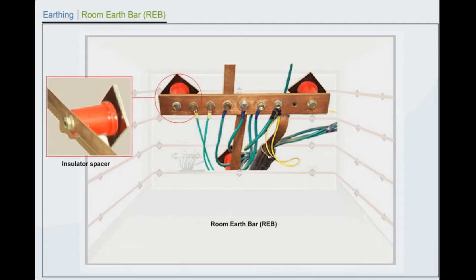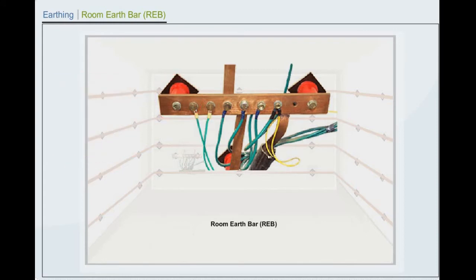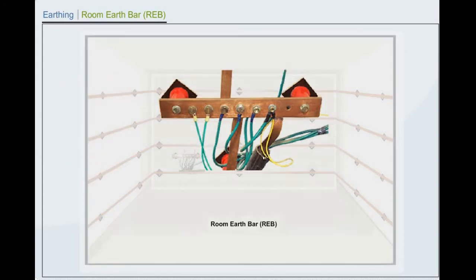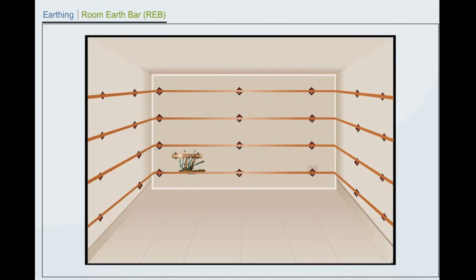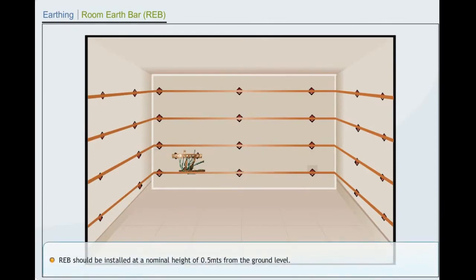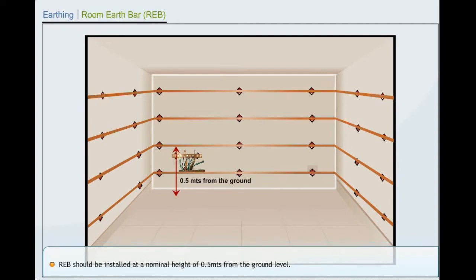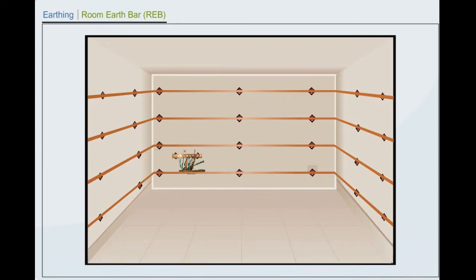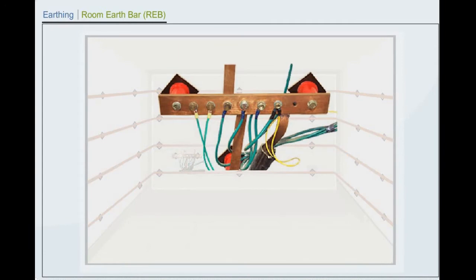Each room earth bar shall be installed against the wall with low voltage insulator spacers of height 60 mm. It should be installed as per the site convenience, but the lead length should be very less. The REB should be installed at a nominal height of 0.5 meters from the ground level. All terminations on the room earth bar shall be by bolted lugs with spring washers.